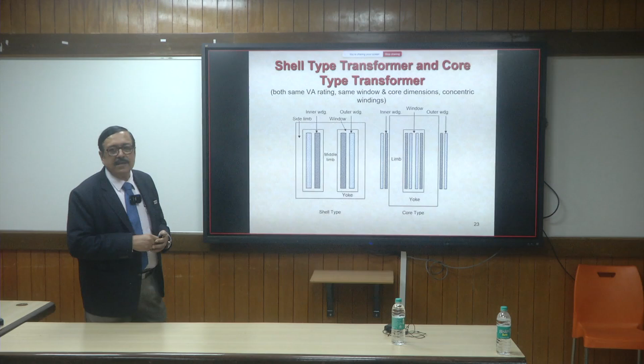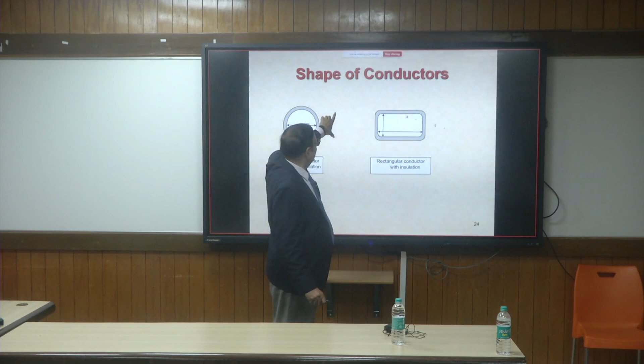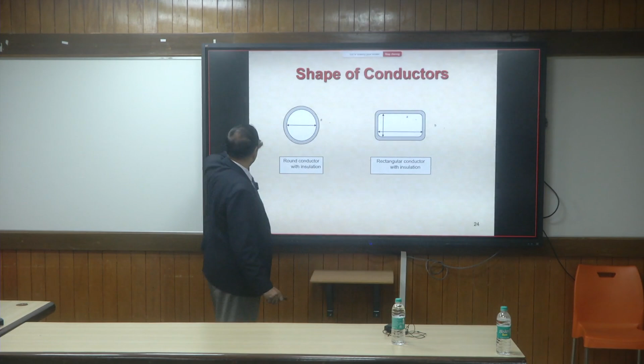Now we come to conductors. What shall be the shape of the conductor that you want? Whether it should be a round conductor or a rectangular conductor. It's not really a matter of choice. It comes from utilization, the effectiveness. I would like to use a rectangular conductor because the next conductor I place next to it has very little space in between. So wastage of space is the minimum. What we call window utilization is the maximum in rectangular conductors. If I place another round conductor next to it, there is a lot of V-shaped area which is lost. So I would like to have a rectangular conductor.